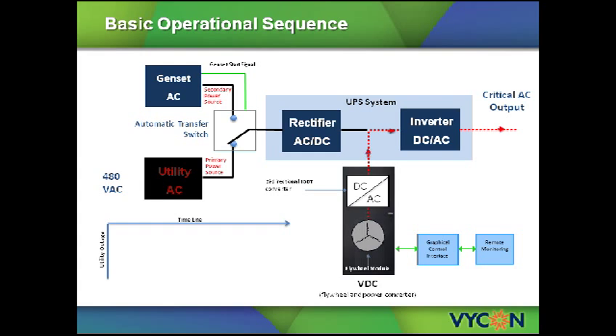While the flywheel is providing the backup energy to the critical loads through the UPS inverter, the ATS waits a couple of seconds after the utility outage occurs to confirm that the utility power has indeed failed and is not simply a short glitch. If the utility has not returned within those 2 seconds, then the ATS sends the start signal to the standby diesel generator to start. Once the start signal is received, it will take approximately 5 to 6 seconds for the generator to come up to its operating speed and be able to provide power to the UPS.